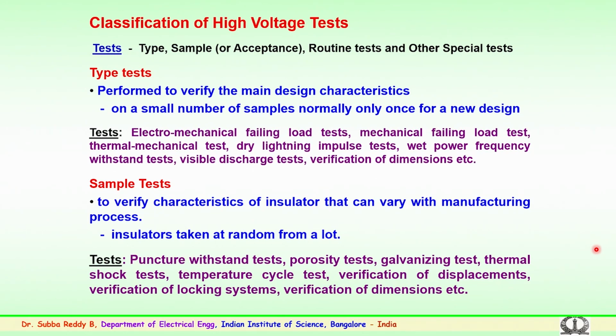The thermal shock test helps show whether the insulator can take this type of load in the field. In the temperature cycle test, a temperature higher than the operating temperature in the field is applied for a known period of time, and the insulator is verified for whether it can withstand it over a specified period. Then there is verification of the various locking systems, cap and pin, and metallic hardware. Verification of dimensions and so on falls under this acceptance or sample test category.